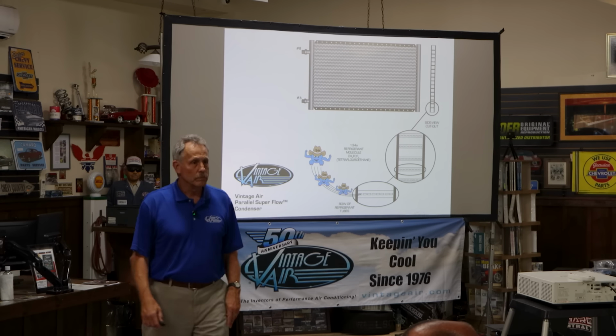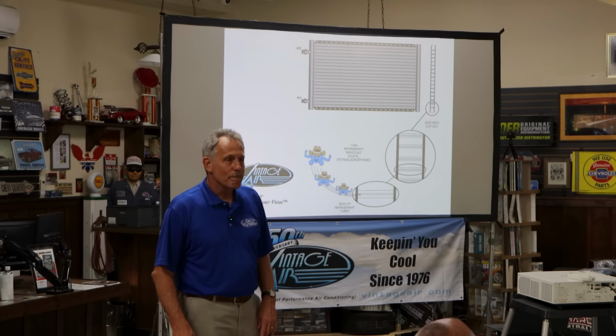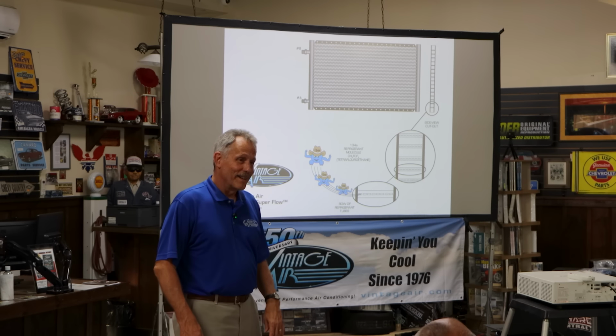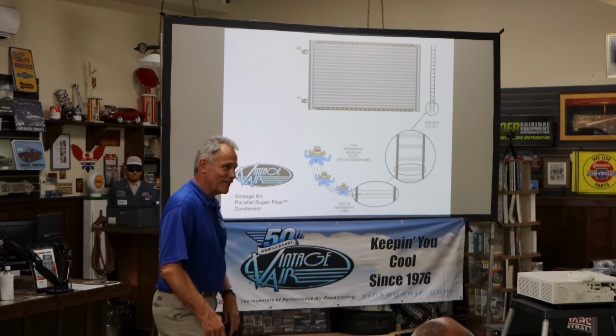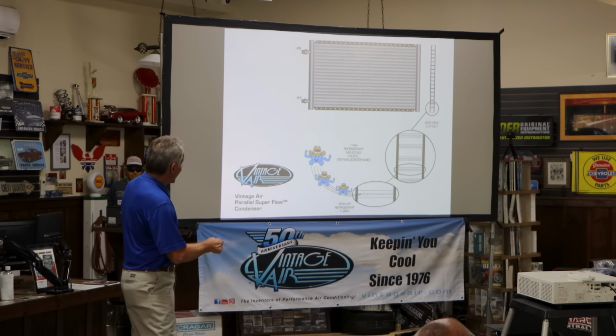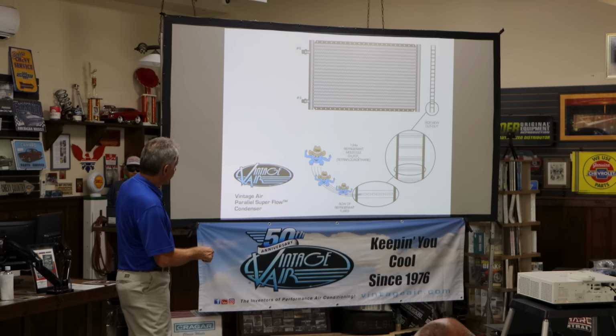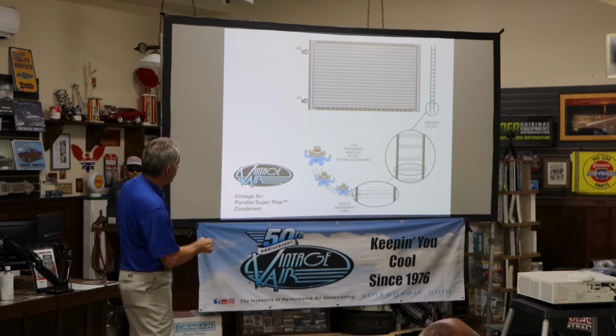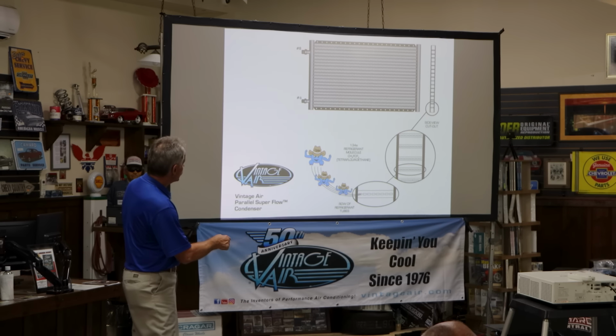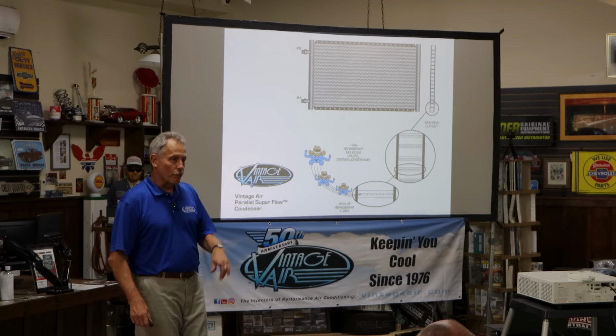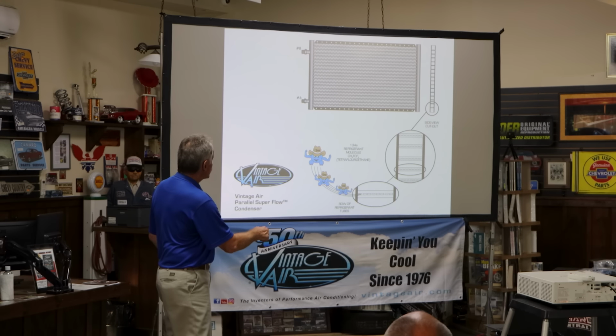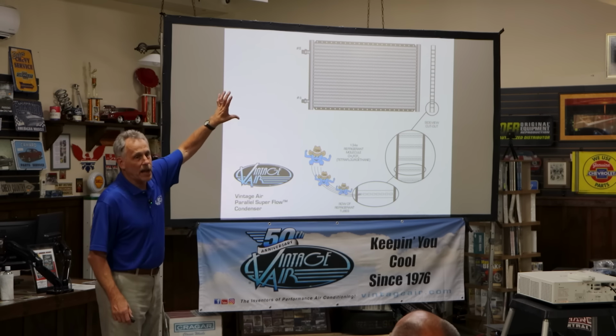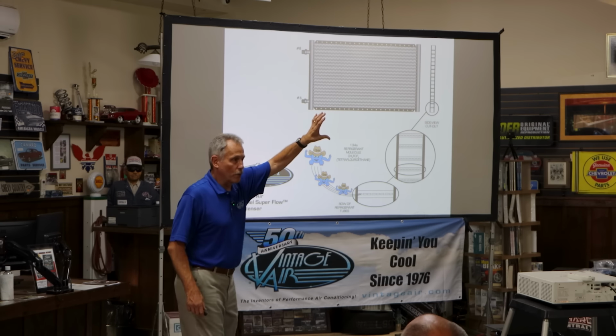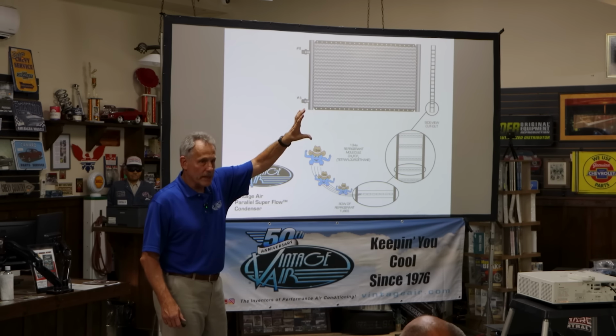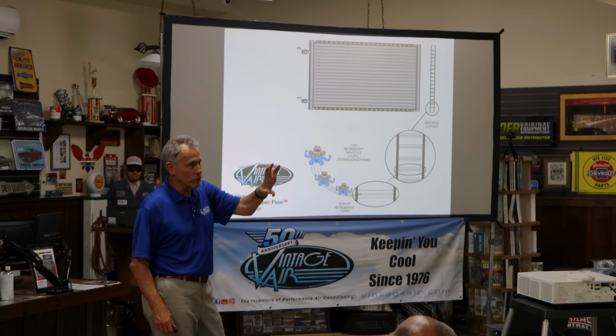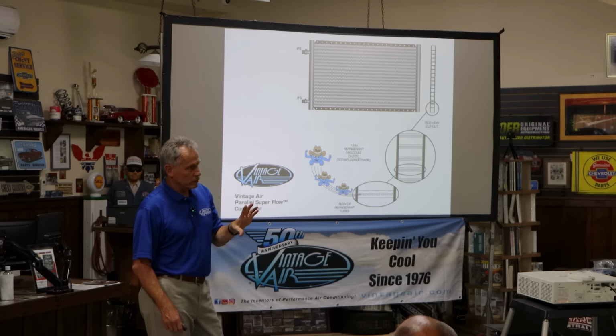Does it matter if the orientation of the inlet and outlet is there? Yes, and I'm going to talk about that right now. You got a number 8 on the top and a number 6 on the bottom. The number 8 is coming from the compressor, that's the larger hose, and the number 6 is on the bottom. The reason for this is we're putting a high pressure gas in the top, and as we're running ram air through there, we're taking the heat away and condensing that gas to a liquid. Which is heavier, gas or liquid?